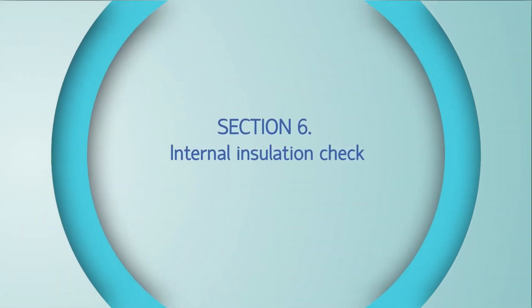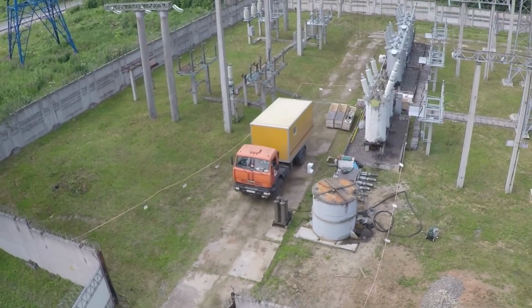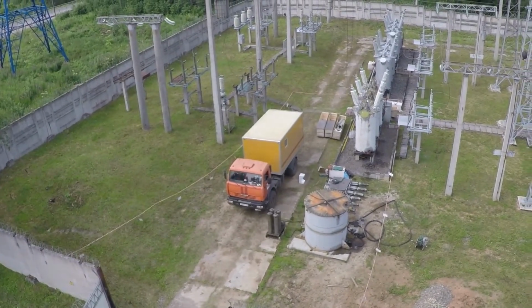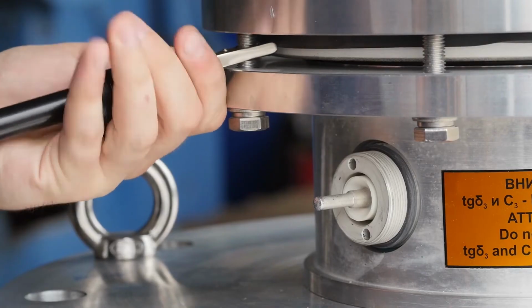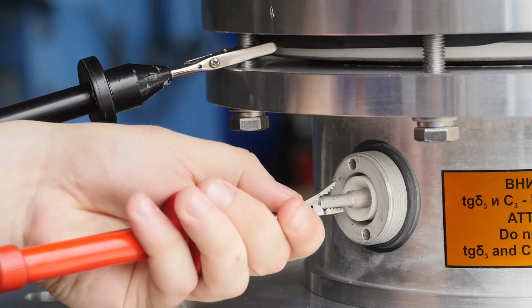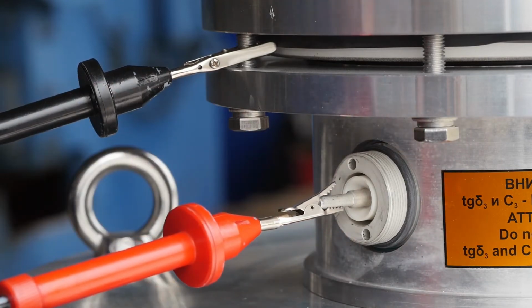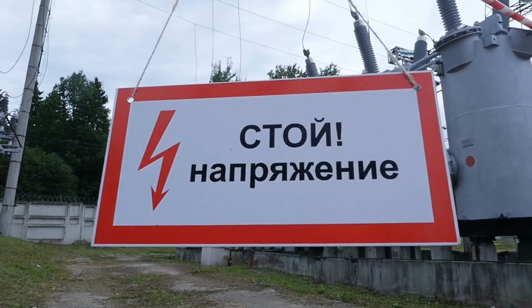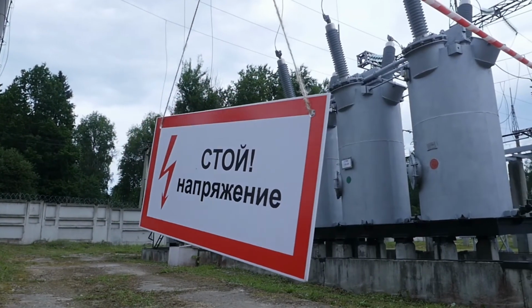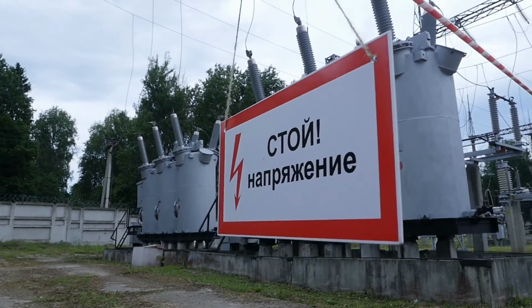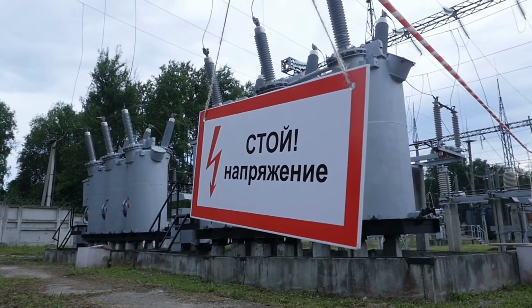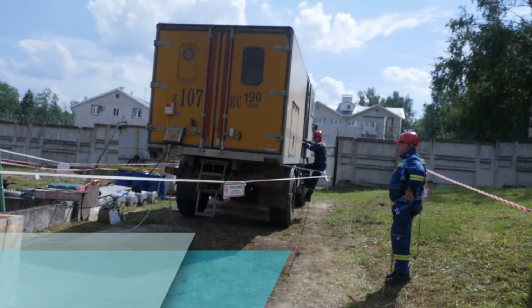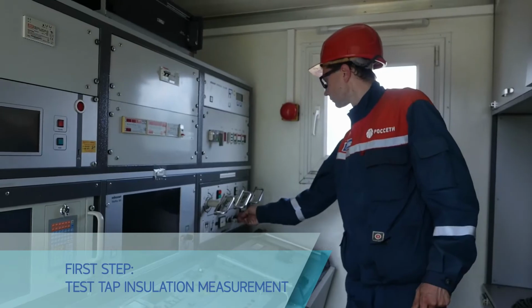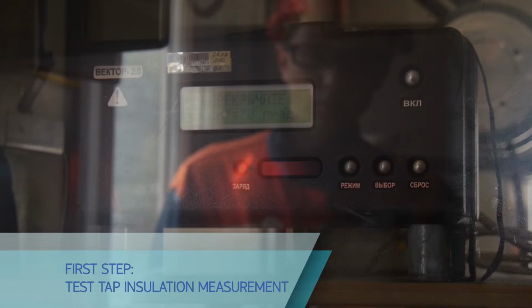Internal insulation check. Perform bushing measurements. While carrying out electrical measurements to estimate a technical condition of the bushing, follow safety regulations for the operation of power plants of electric power stations and substations, and safety regulations for power plant operation. Internal insulation of the bushing is measured in several steps. The first step, measure the test tap insulation. The surface of the test tap insulation to be measured shall be dry and clean.